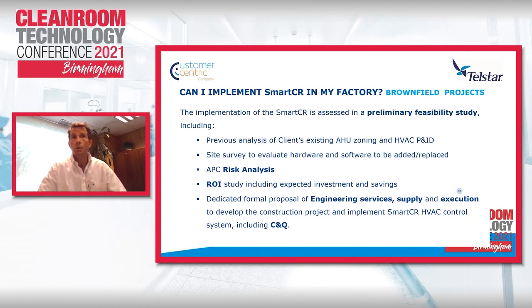If we are talking about aseptic areas or sterile areas where most of it are class B, also the additional investment is not that big, because the particle counters have to be there anyway. If we are talking about class C or class D areas, then the smart clean room requires to install particle counters where in a conventional scenario you will not consider, and then the investment will be bigger.